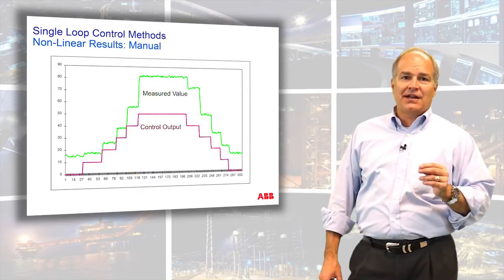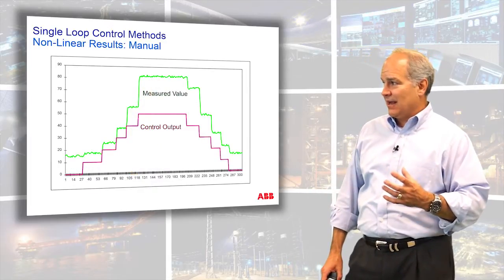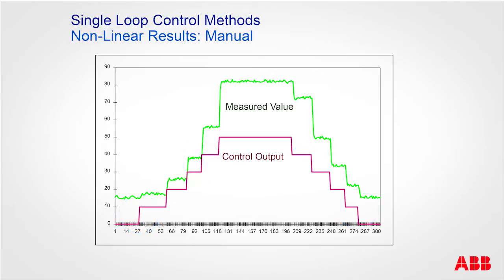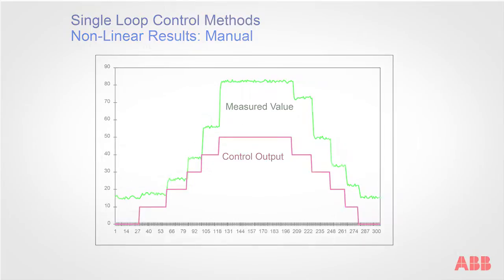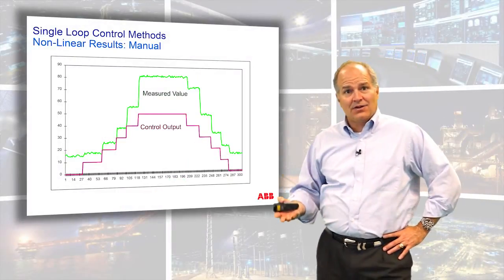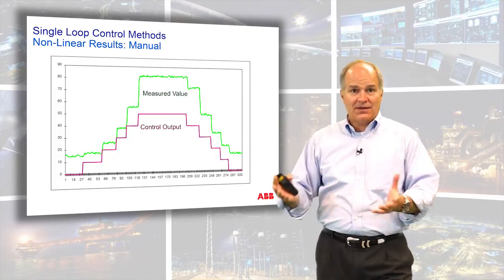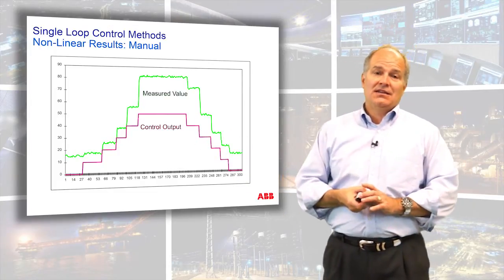Another nonlinearity can come in the process gain. Notice each of these steps in the output are the same size. Over here I made a change and it moved just a little bit; here it moved more, more, more, and then it moved a lot. So this is where we've got a nonlinear process gain. The process literally changes a different amount depending upon the same change in the actuation device.